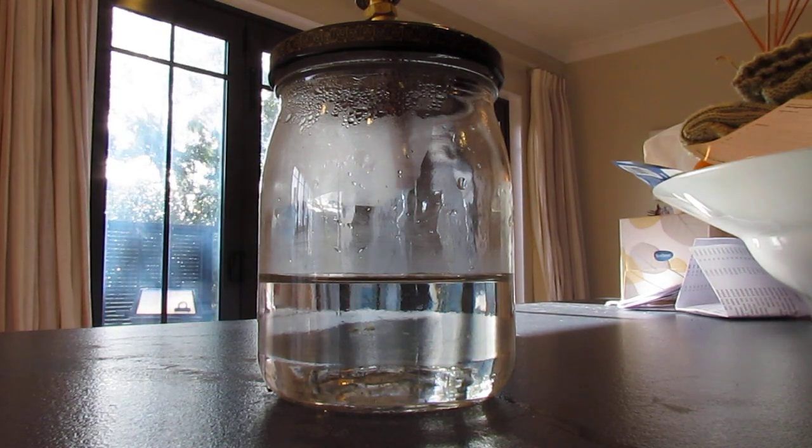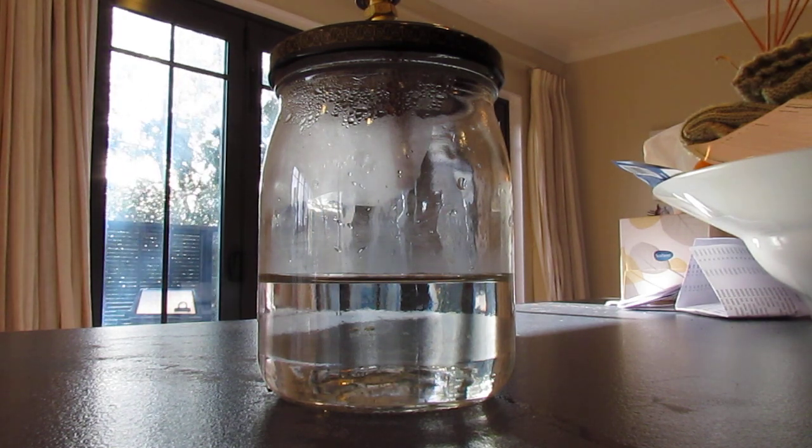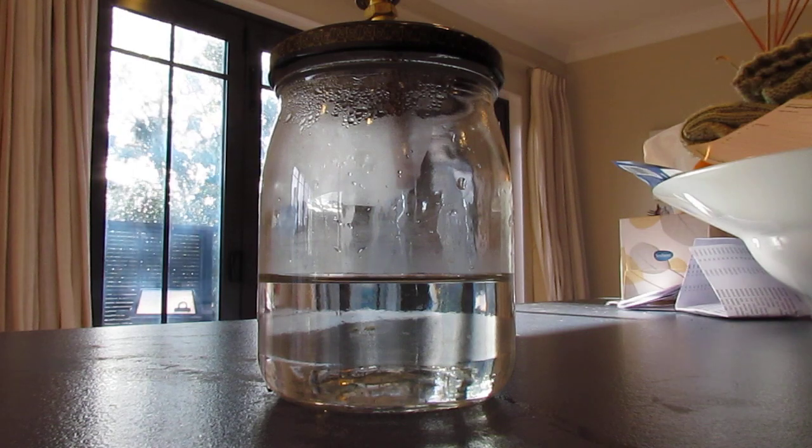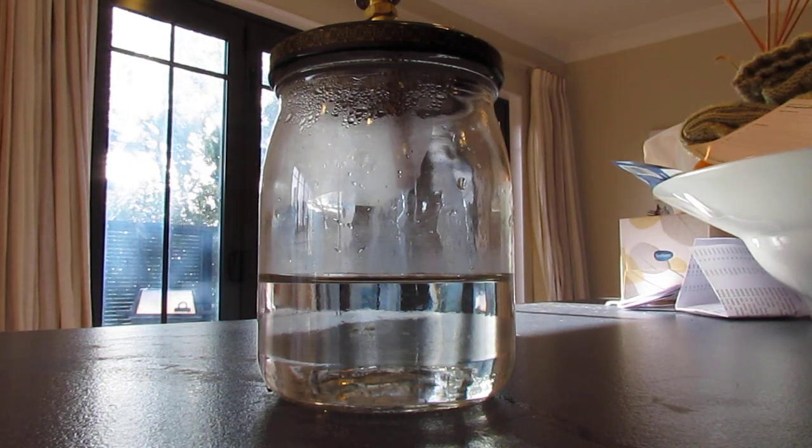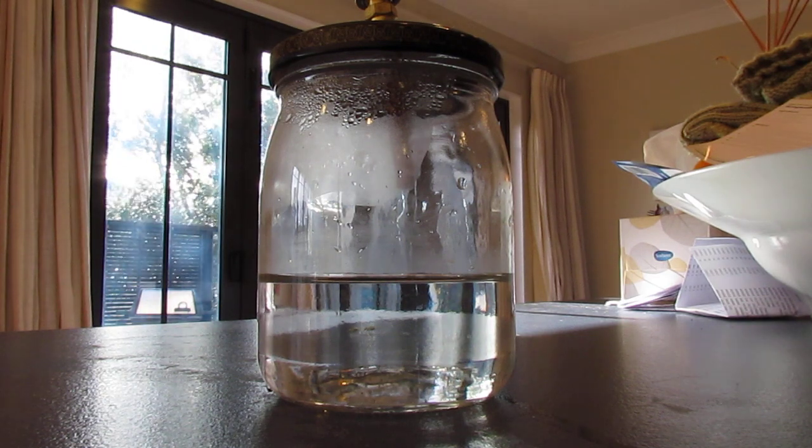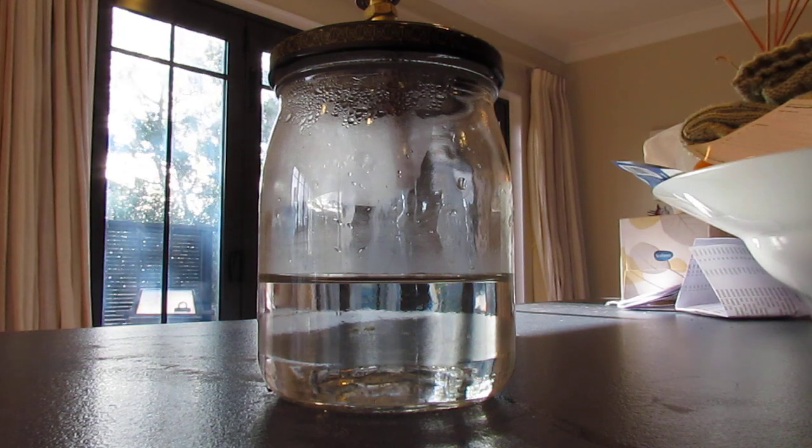But when we go into a refrigeration system, we can actually put a vacuum onto that and lower the pressure, causing moisture to bubble off at room temperature. And so to prove that, I put together this little something you can look at to visually see what happens to moisture in the refrigeration system.